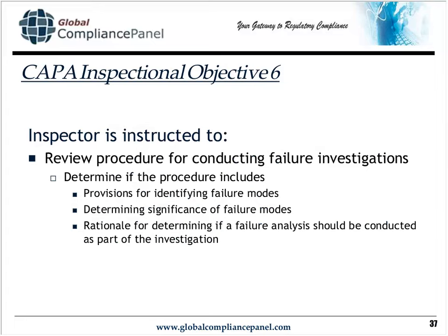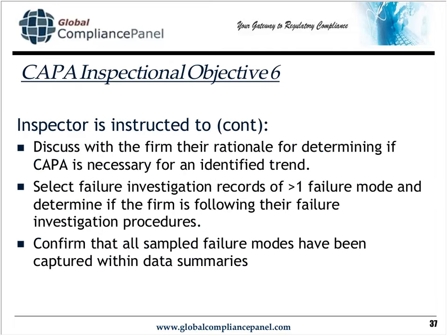You've got to have provisions for identifying failure modes. You've got to determine the significance of those failure modes. Every failure mode, every type of failure, does not have the same significance. Some have greater patient safety risk associated with them, for example. And the inspector will take a look at how you determine whether you need to conduct a failure analysis as part of the investigation.